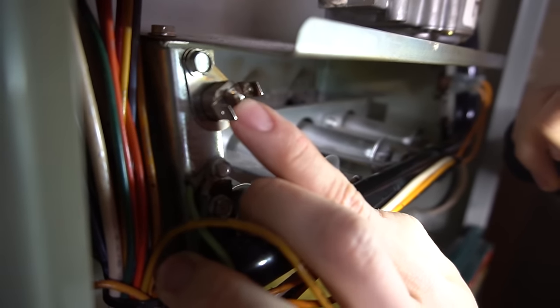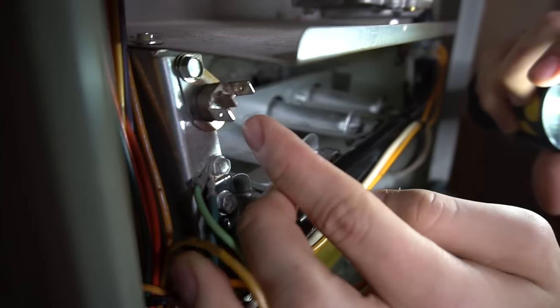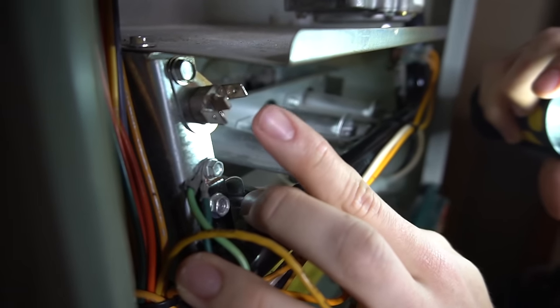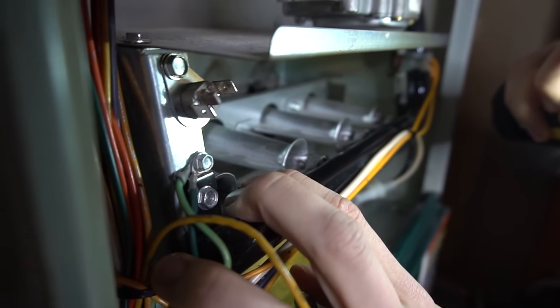This means that if they ever trip, you have to manually reset them. That's why there's a little button right on top of them. If your flame rollout switch is tripped, this button will be popped out. If you press it in, that will reset it and your furnace will come back on.